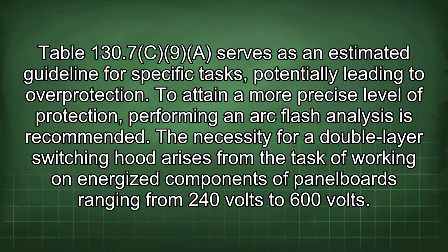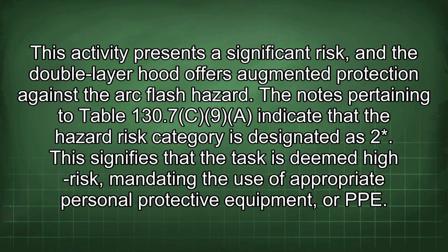130.7c9 serves as an estimated guideline for specific tasks, potentially leading to overprotection. To attain a more precise level of protection, performing an arc flash analysis is recommended. The necessity for a double-layer switching hood arises from the task of working on energized components of panel boards ranging from 240 volts to 600 volts. This activity presents a significant risk, and the double-layer hood offers augmented protection against the arc flash hazard.